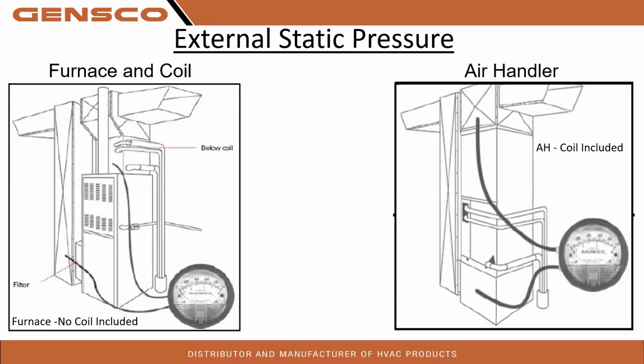Air handler. So with furnaces, our design static pressure is just for the furnace because the coil is external and you might not have a coil on it. Air handlers have the coil built in, so it is manufactured and tested with the coil in place. So therefore, we're just taking it again before the filter and right above, right? So you got your supply and return, and you're going to add them together for your total external. So again, the air handler has the coil included, so it's tested with the coil.